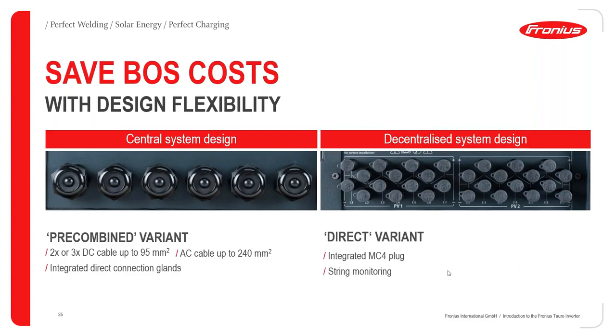The decentralized version or the direct version will also offer one more advantage, that will be the possibility for you to do direct string monitoring. Because the strings are directly connected to the inverter, it will be possible for you to achieve string level monitoring. So that makes it even more flexible as far as monitoring is concerned. The cable size remains the same for the AC side, but you have for string protection also the possibility to use string fuses, and depending on how much power or current you're feeding per string, you can freely select the amperages of the fuses to be used.